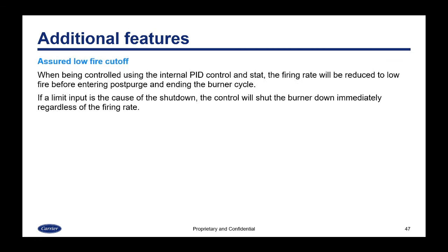When being controlled using the internal PID control and stat, the firing rate will always be reduced to low fire before entering post-purge and ending the burner cycle. This is known as assured low fire cutoff. If a limit input is the cause of the shutdown, the control will shut down the burner immediately regardless of the firing rate, because that is from an external source.